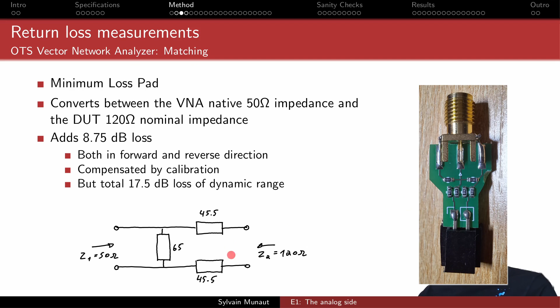because you basically perform the calibration with the minimum loss pad, and then you perform the short, the open, and the load on the 120 ohm side.